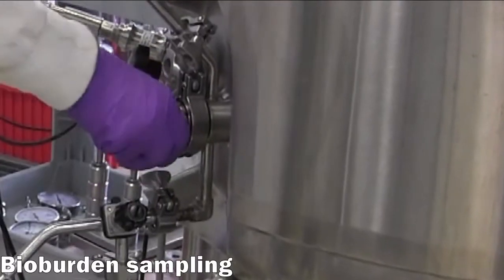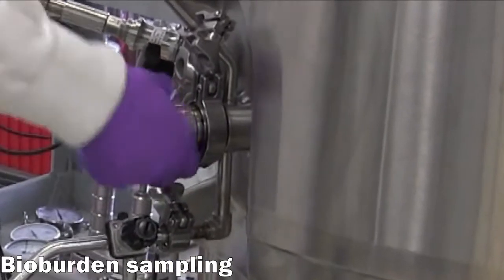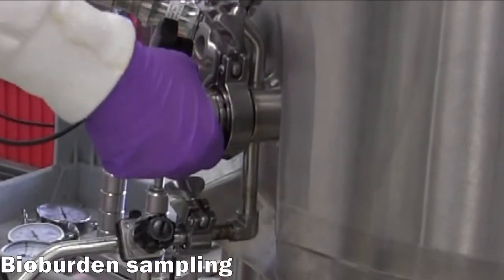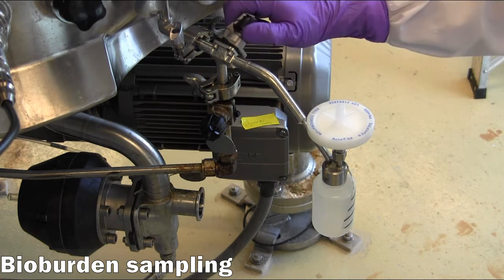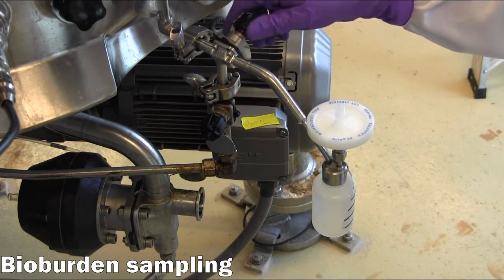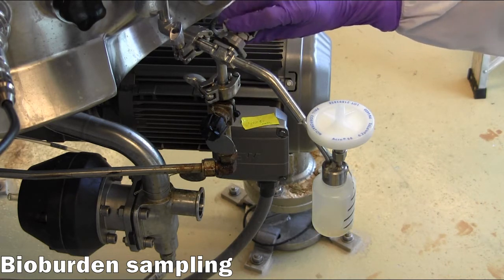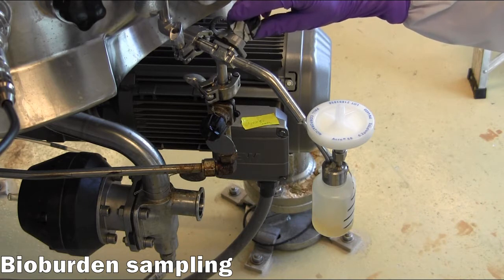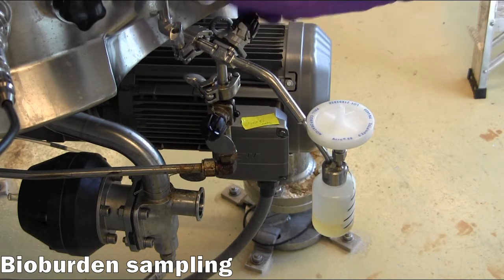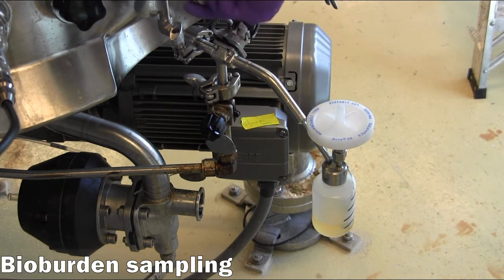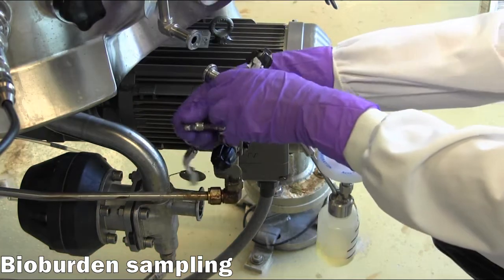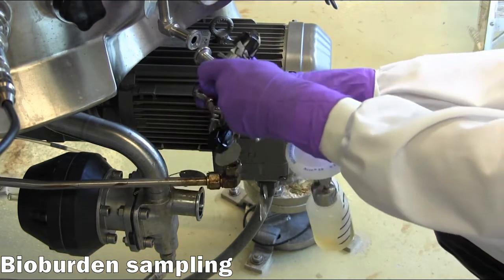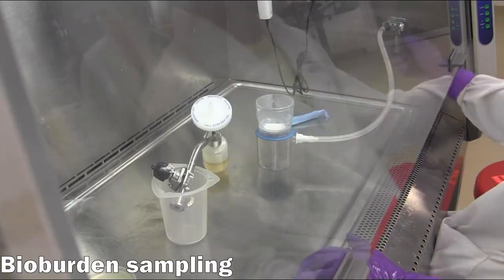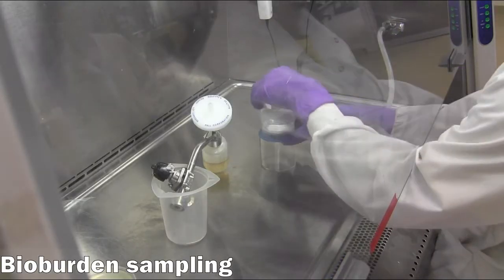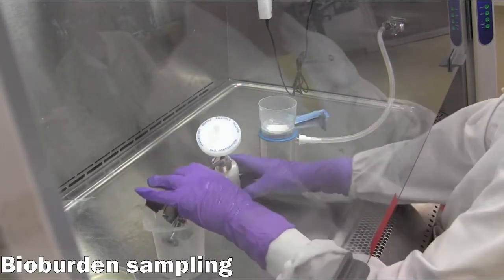For checking the growth media's sterility, take a sample by opening the sample port on the vessel, then open the hand valve on the bioburden assembly and aseptically fill the plastic bottle with media. Close the sample port and the hand valve, then remove and transfer the whole of the bioburden assembly to the nearest biosafety cabinet. Filter the media using a sterile 0.2 micron vacuum filtration assembly.